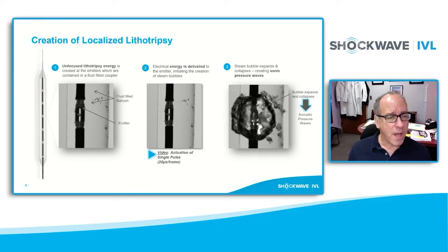In a phantom model, again, the lithoplasty generator is in the center of the screen on the left. This is a movie demonstrating what the energy does inside the vessel wall. You can see the shockwave emitting through the balloon to outside the vessel, and then the acoustic wave collapses almost instantly. This is repeated dozens of times during a treatment within the vessel wall.